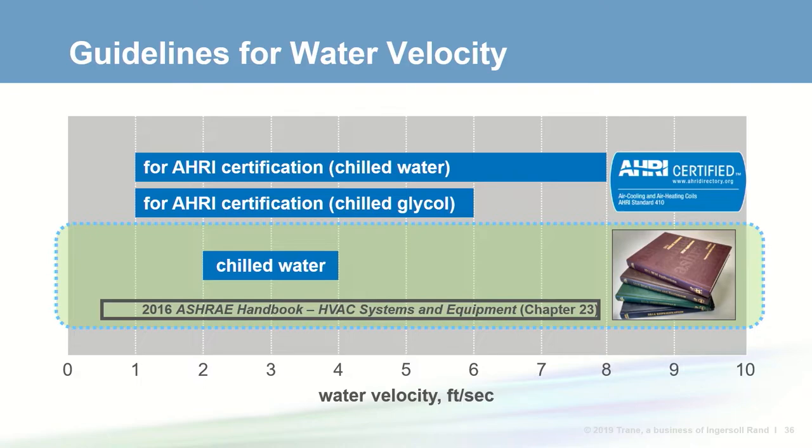The ASHRAE handbook suggests cooling coils are best selected with water velocities between 2 and 4 feet per second, providing a good balance between coil size and minimizing air and water pressure drops. Water velocity is also a key factor for flow turbulence — along with fluid density, viscosity, and tube diameter. As turbulence of the moving fluid increases, so does its ability to transfer heat. Some in the HVAC industry have expressed concern that coil heat transfer will deteriorate if the Reynolds number falls into the laminar flow region.